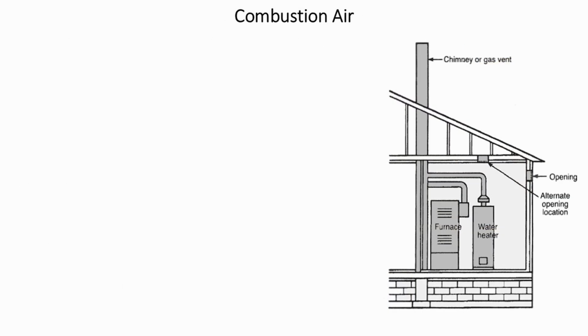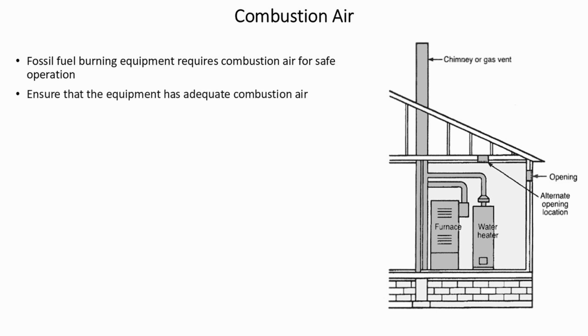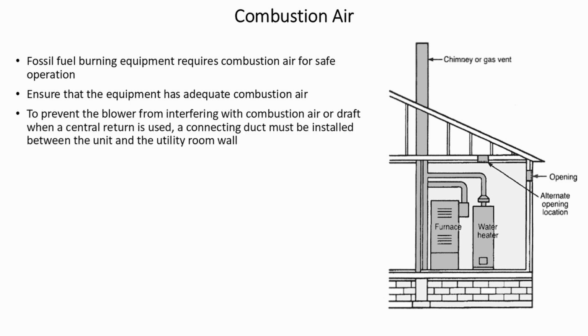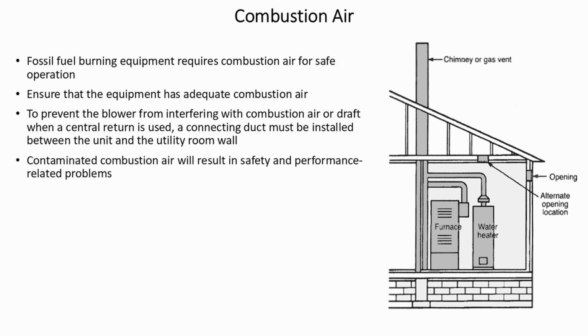Combustion air. Fossil fuel burning equipment requires combustion air for safe operation. Ensure that the equipment has adequate combustion air. To prevent the blower from interfering with the combustion air or draft when a central return is used, a connecting duct must be installed between the unit and the utility room wall. Contaminated combustion air will result in safety and performance-related problems.